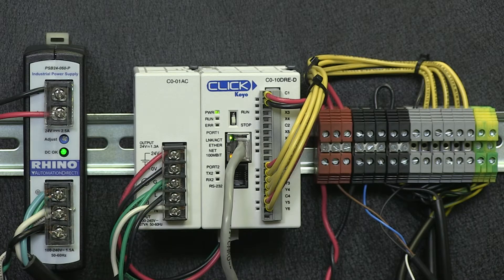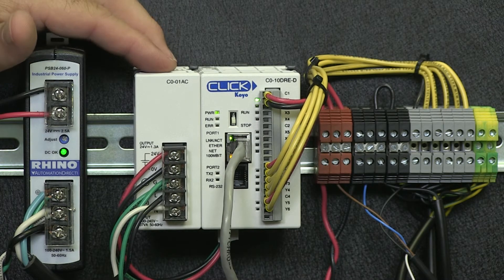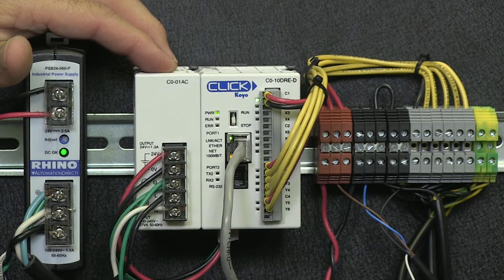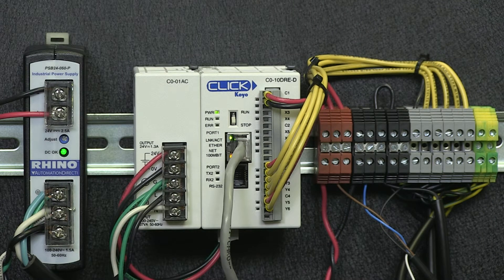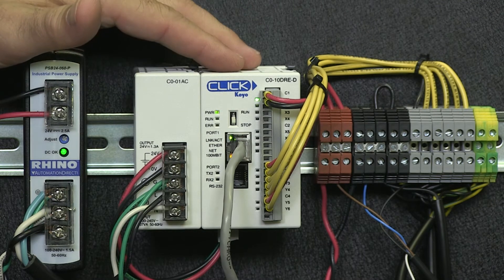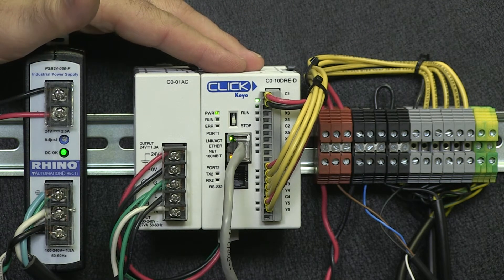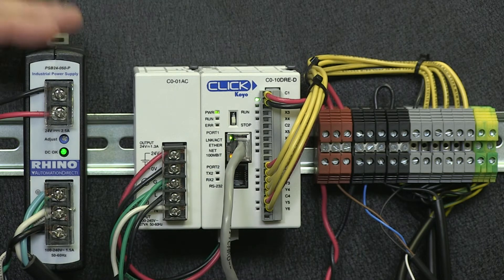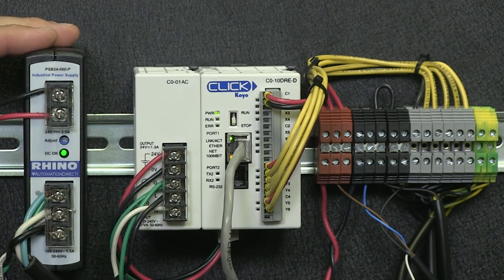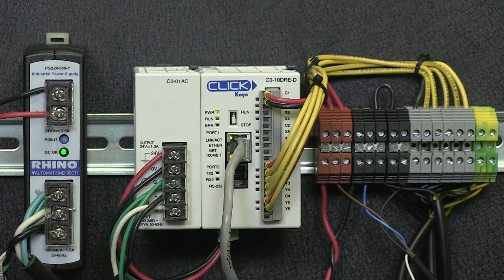Since we have 120 volts AC supply voltage, we need to use this Click power supply because the Click PLC requires 24 volts DC to operate. You may be thinking, why didn't we omit this part and just power our Click PLC from the main 24 volt DC Rhino power supply? Well, we could have, but it's not good practice to have your control power and your I/O power on the same source.